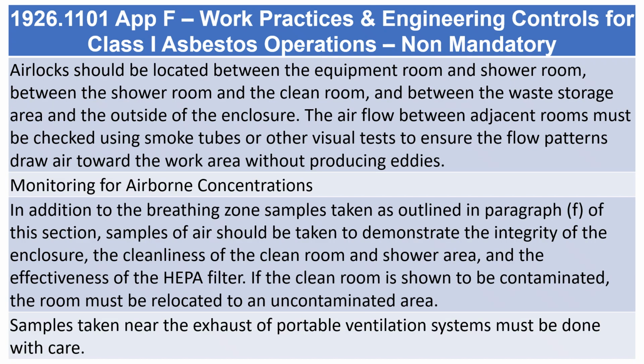Airlocks should be located between the equipment room and shower room, between the shower room and the clean room, and between the waste storage area and the outside of the enclosure. The airflow between adjacent rooms must be checked using smoke tubes or other visual tests to ensure the flow patterns draw air toward the work area without producing eddies.